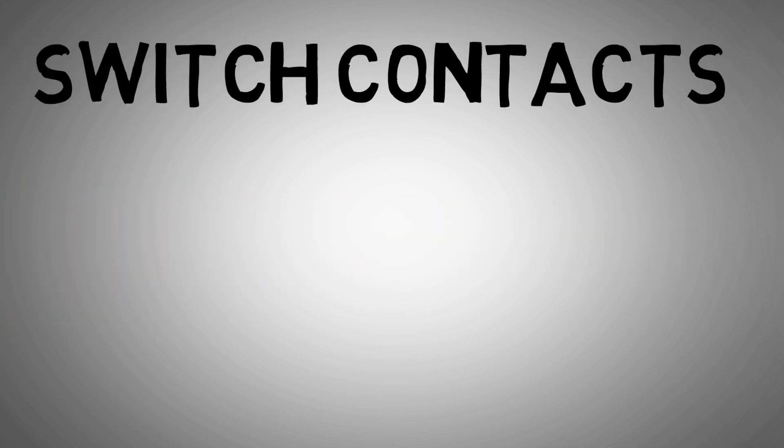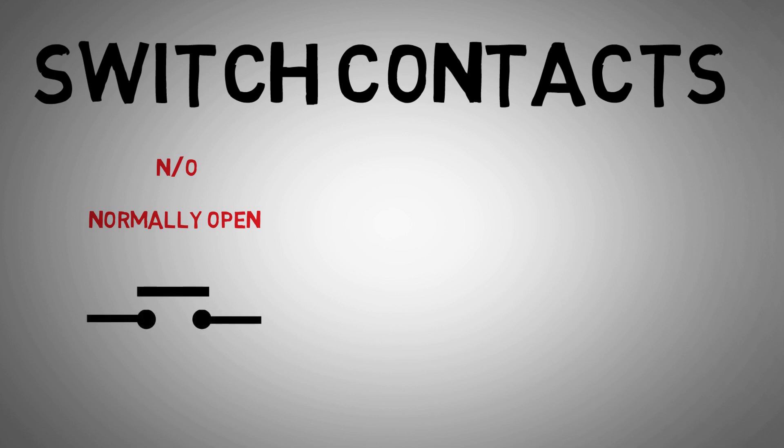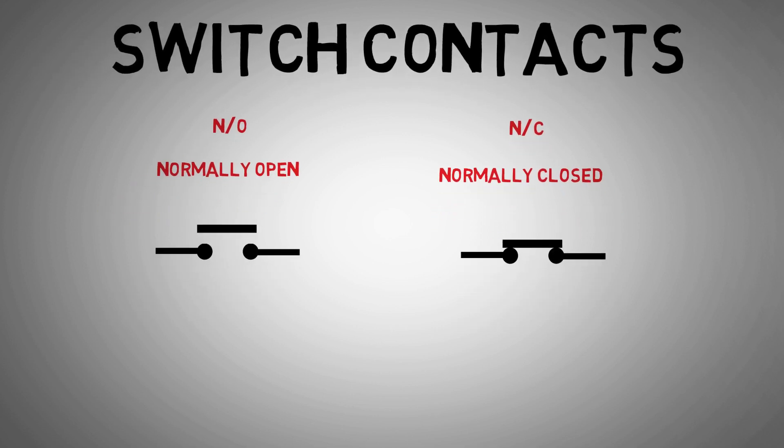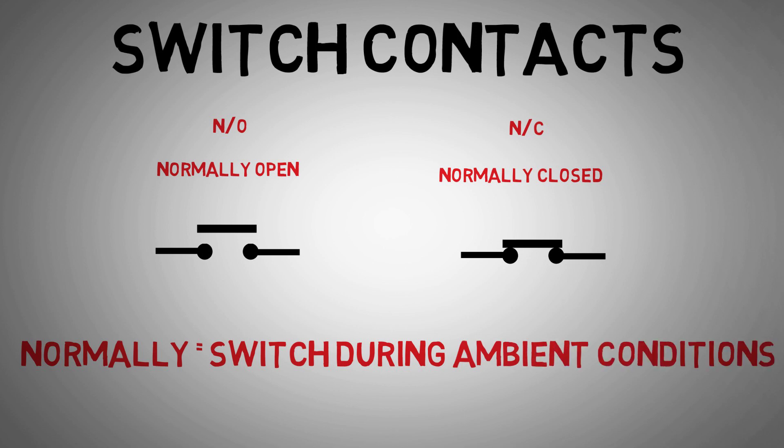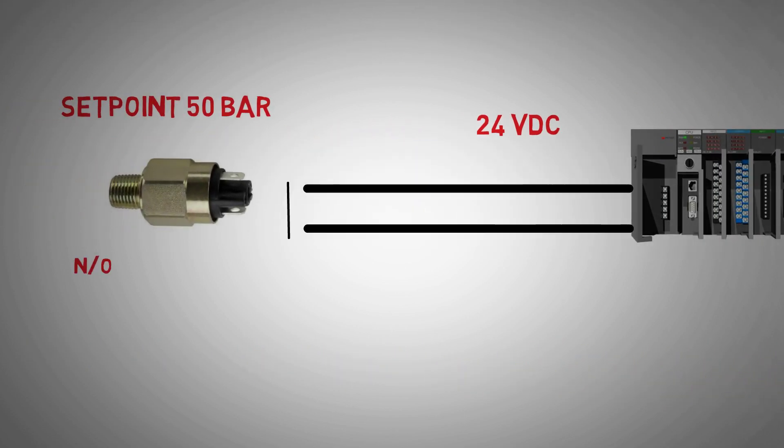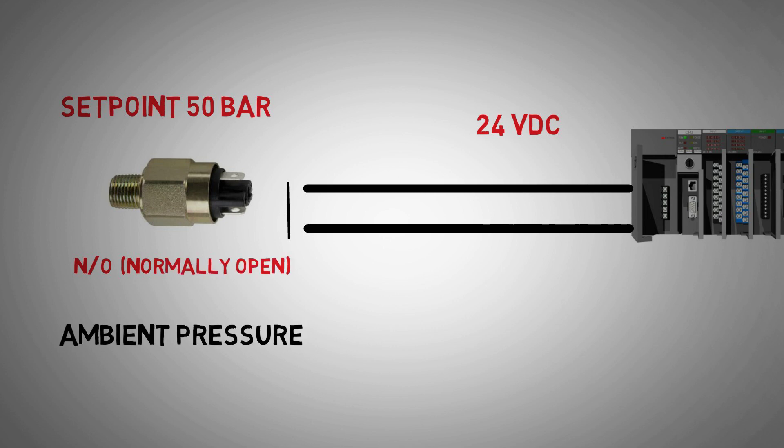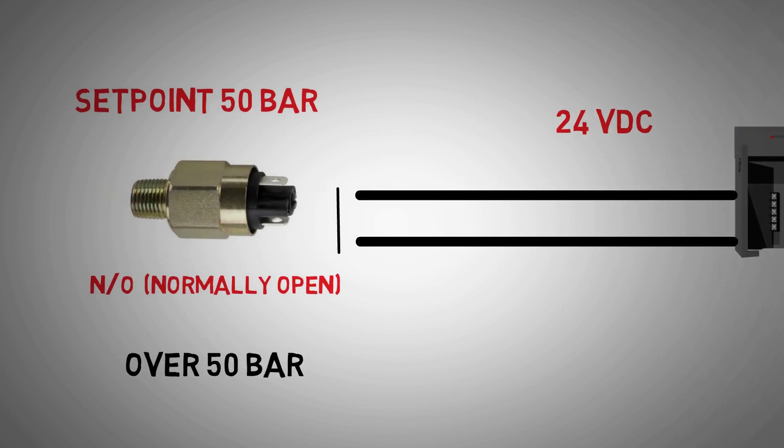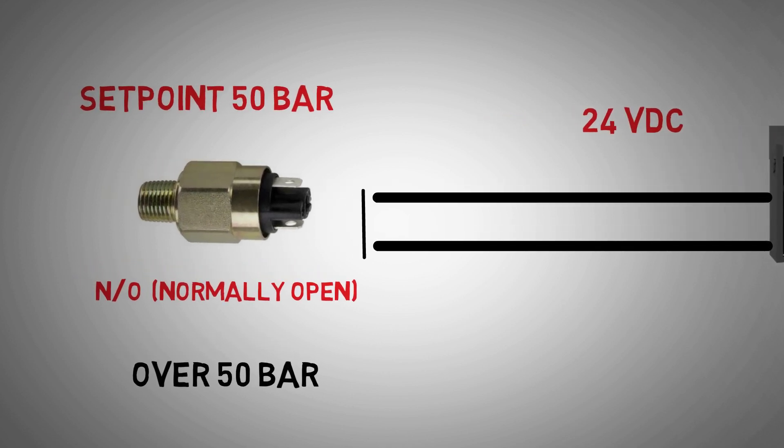Electrical switches are usually described as normally open or normally closed. The normally refers to the condition of the switch in ambient conditions. If we were to say our 50 bar pressure switch has a normally open contact, then at ambient pressure, the switch contact will be open or unable to conduct electricity. When the pressure is above 50 bar, the switch will be closed or act as a conductor for the electrical current within the loop.